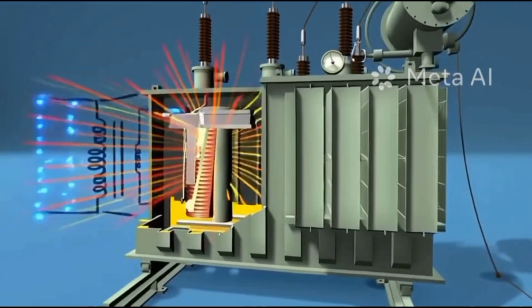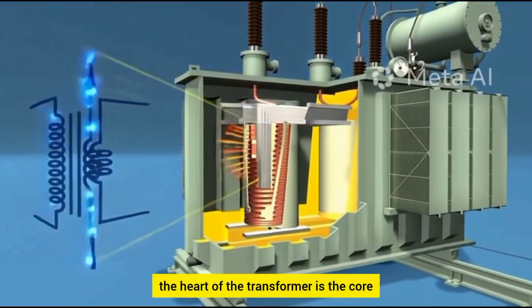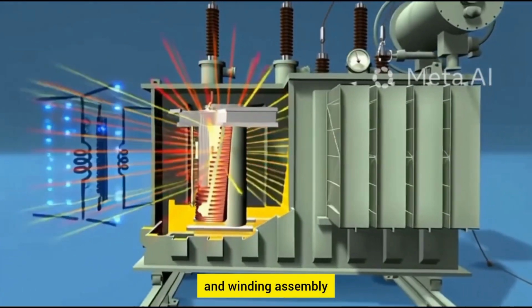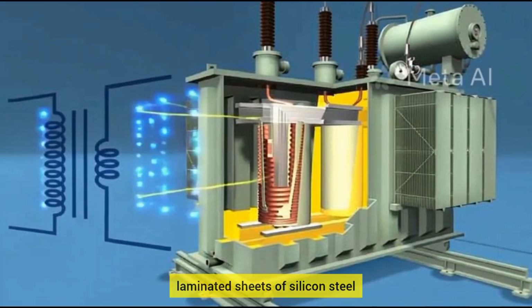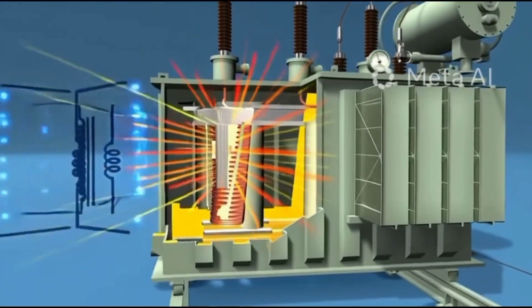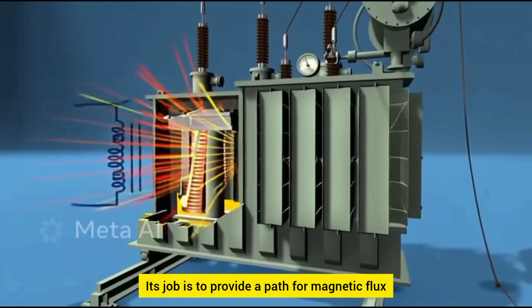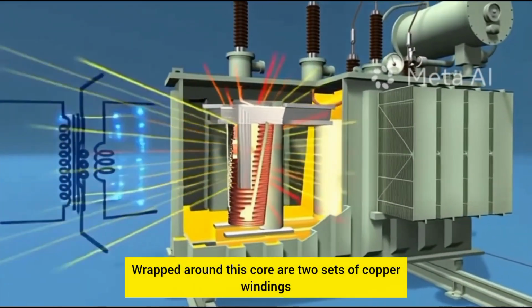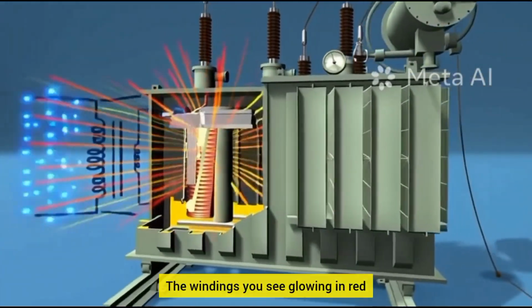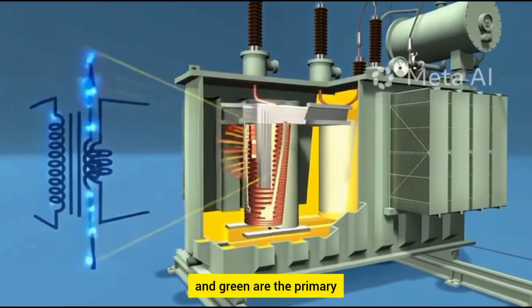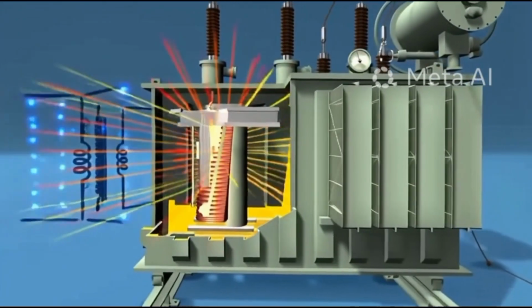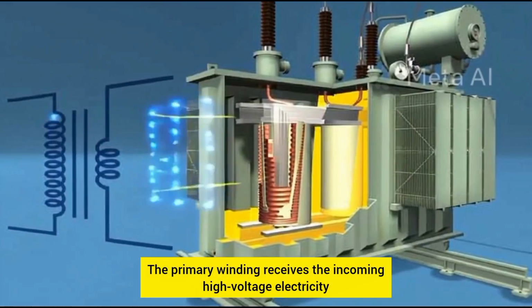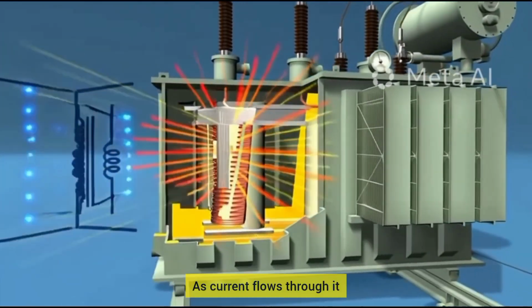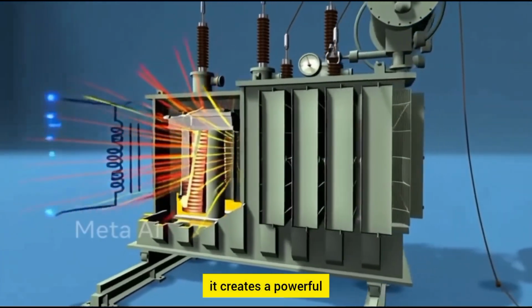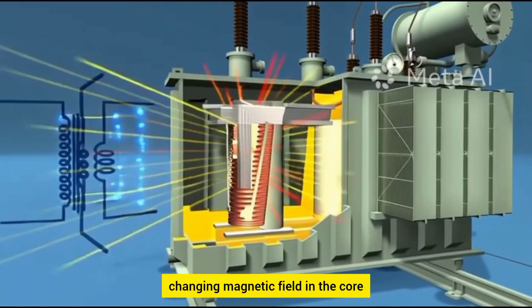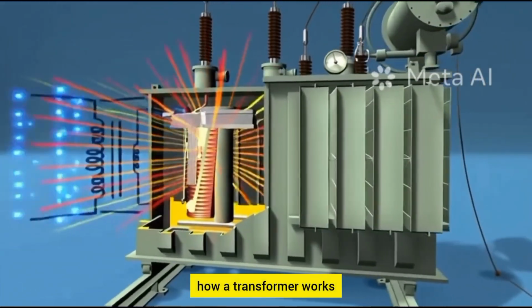dangerous for direct use. Inside the main tank, the heart of the transformer is the core and winding assembly. The core is made of thin, laminated sheets of silicon steel. Its job is to provide a path for magnetic flux. Wrapped around this core are two sets of copper windings. The windings you see glowing in red and green are the primary and secondary coils. The primary winding receives the incoming high-voltage electricity. As current flows through it, it creates a powerful, changing magnetic field in the core. This magnetic field is the key to how a transformer works.